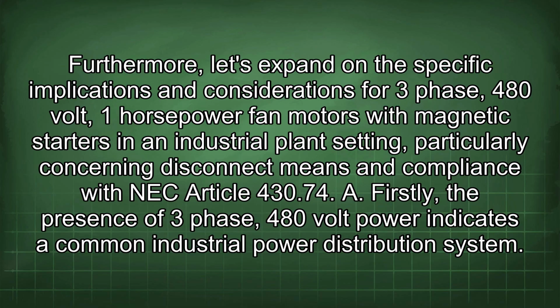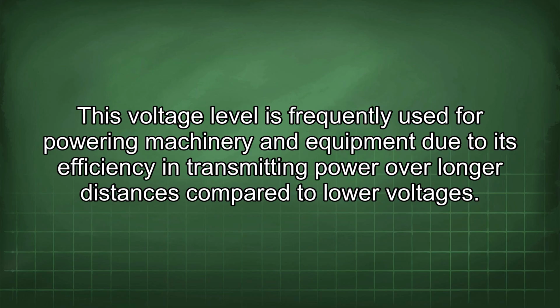an industrial plant setting, particularly concerning disconnect means and compliance with NEC Article 430.74. Firstly, the presence of three-phase, 480-volt power indicates a common industrial power distribution system. This voltage level is frequently used for powering machinery and equipment due to its efficiency in transmitting power over longer distances compared to lower voltages.